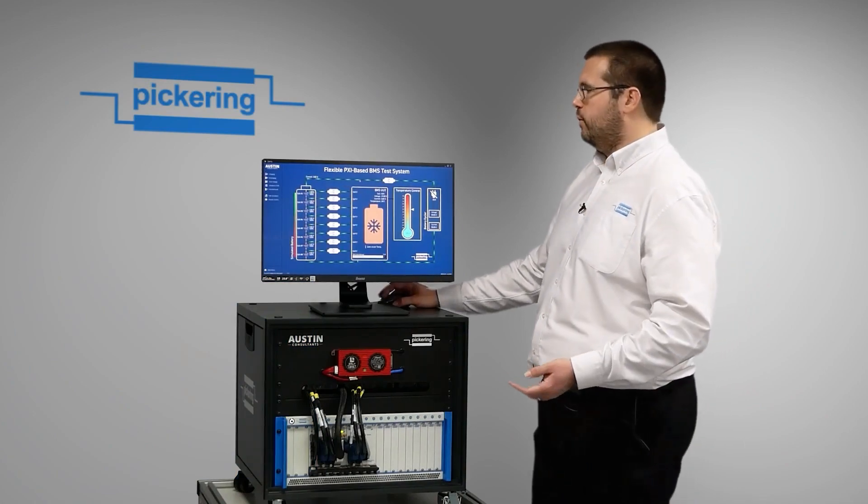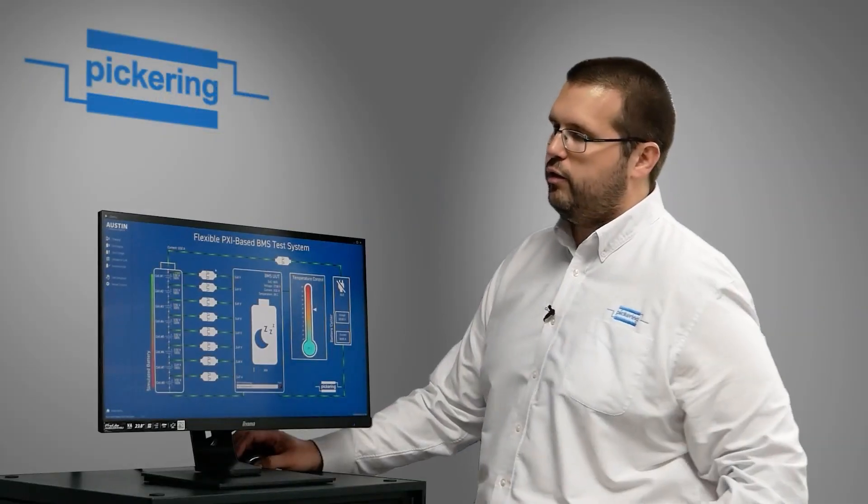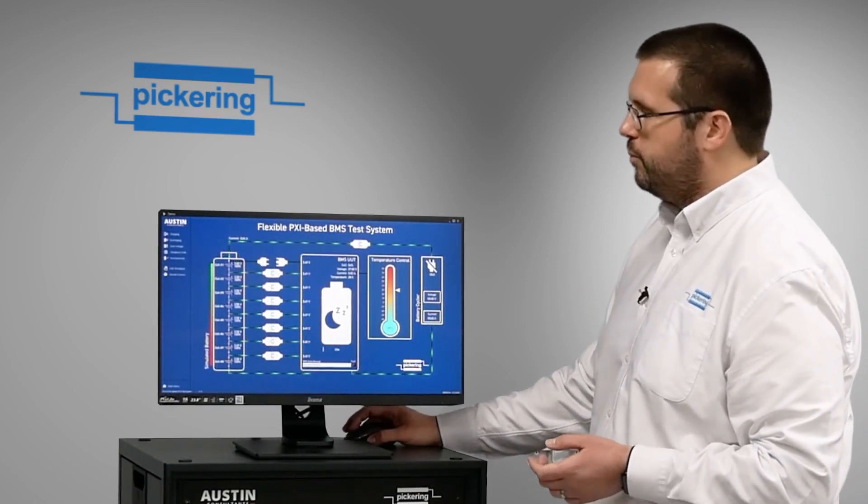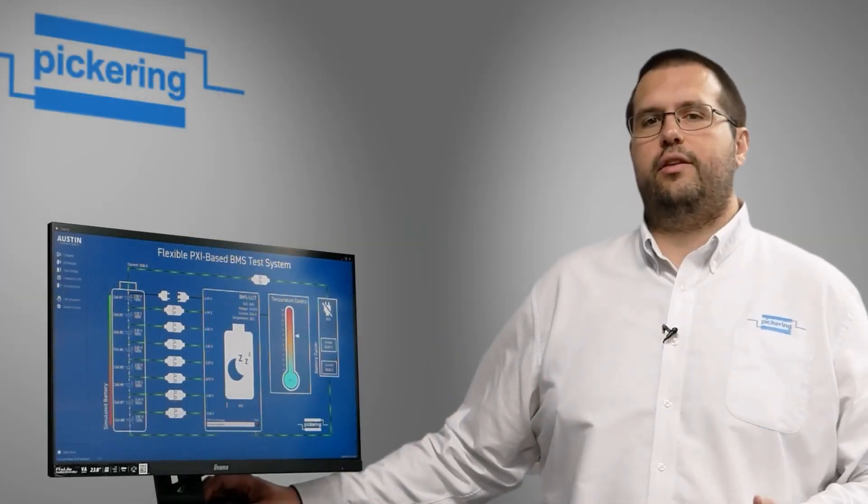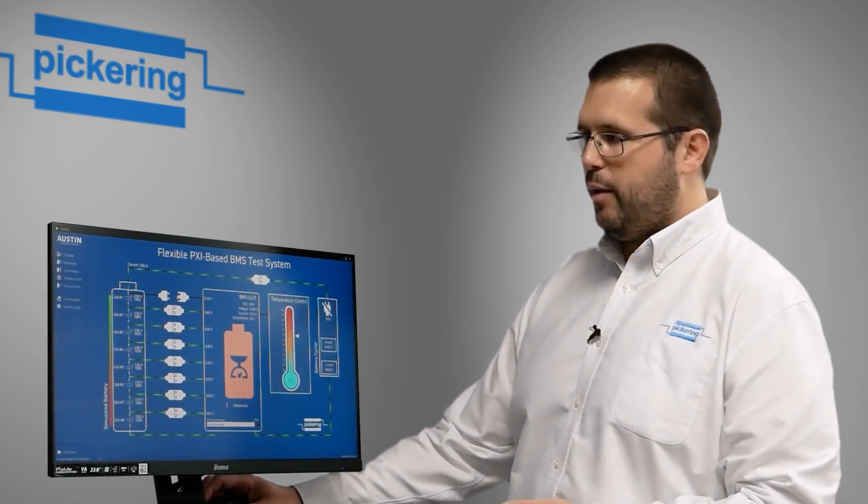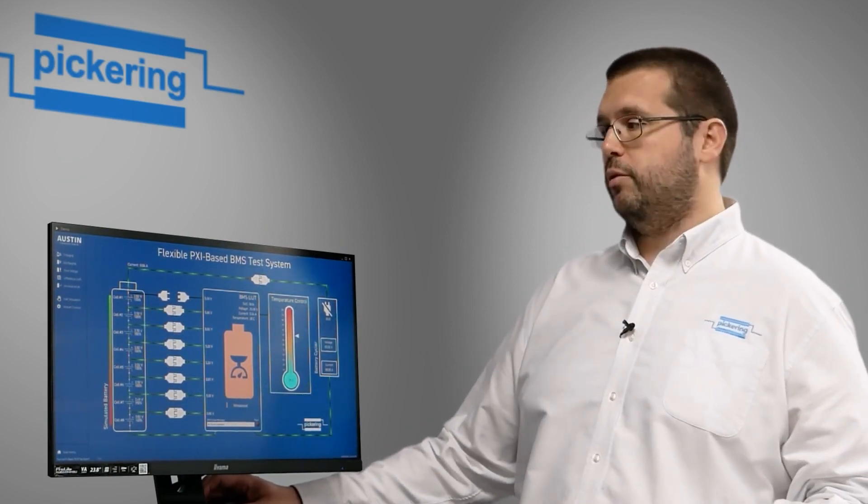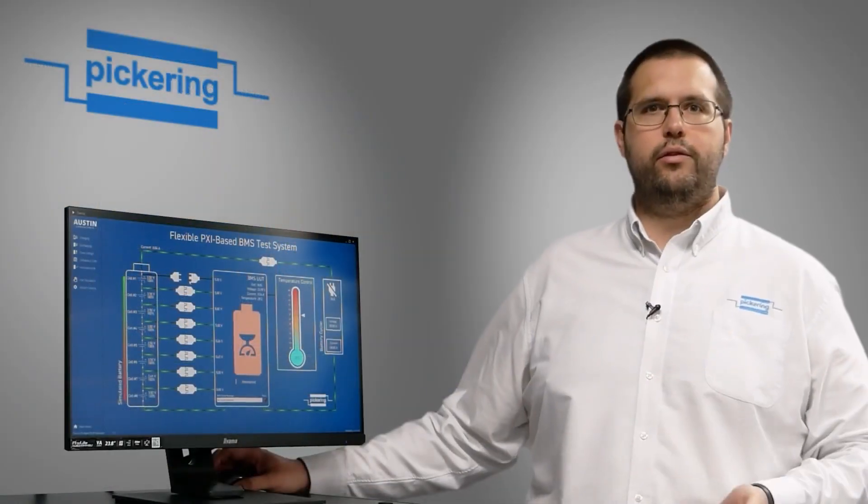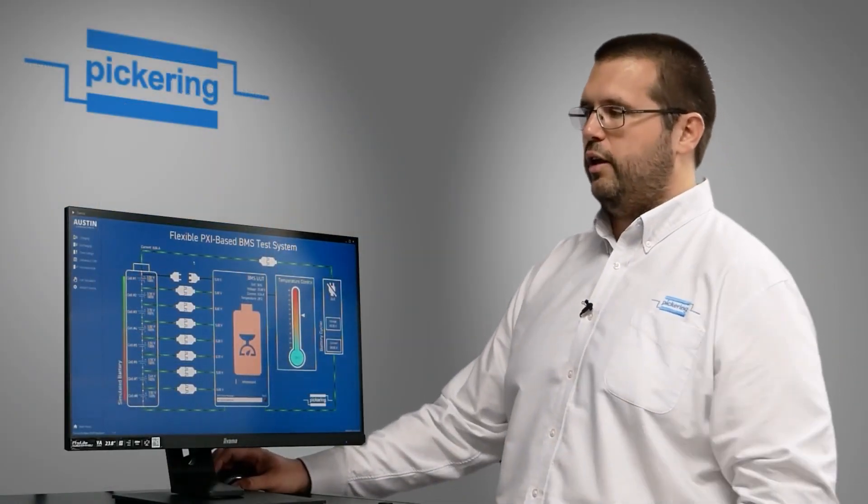Likewise, I mentioned fault insertion before. Each one of these connections is a connection between the BMS and the cell. So if we open one of those, it's basically disconnecting that cell from the BMS through that fault insertion module, and here you can see the BMS is reporting that it's now unbalanced because obviously that cell has been removed.